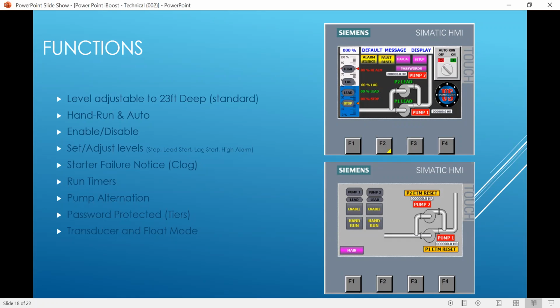TJ Maxx was hacked through the air conditioning unit. So it's very safe, and no one can pull it out of there and attach to their laptop. It won't work. It only works for our IP address. Anyway, it's a neat feature in that I can pull this screen up from my laptop or from a remote building control. Let's say it's the weekend and you've got a building that has a problem with sump and sewage. If you call your service guy, you can say, hey, you're going to need a pump because I can see that pump 1 has failed on the screen.